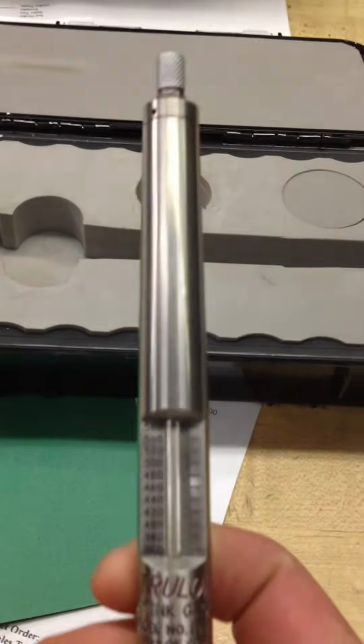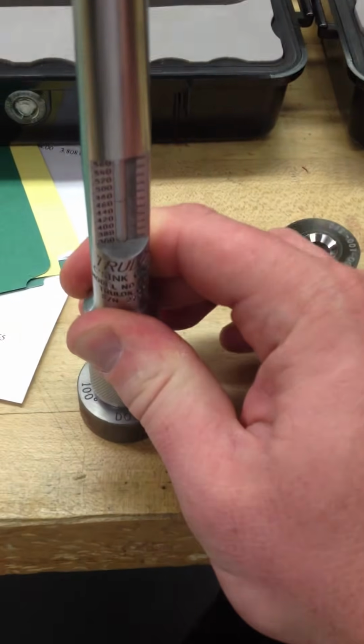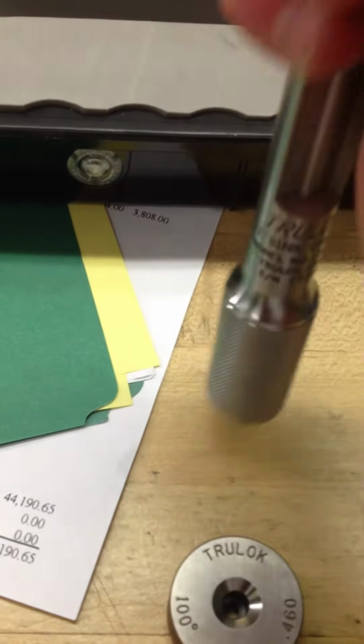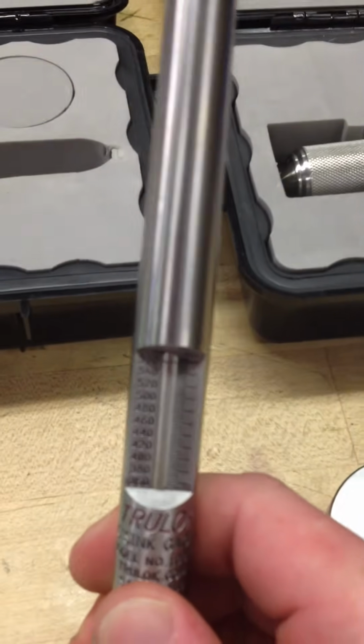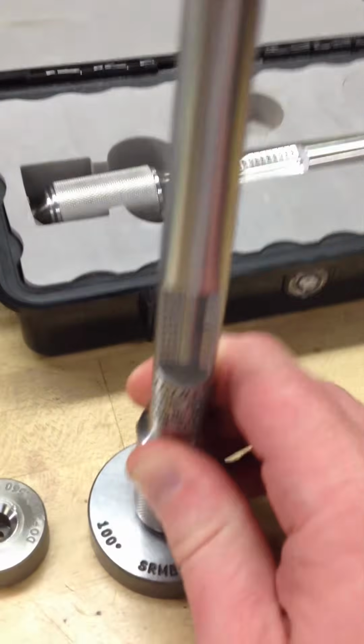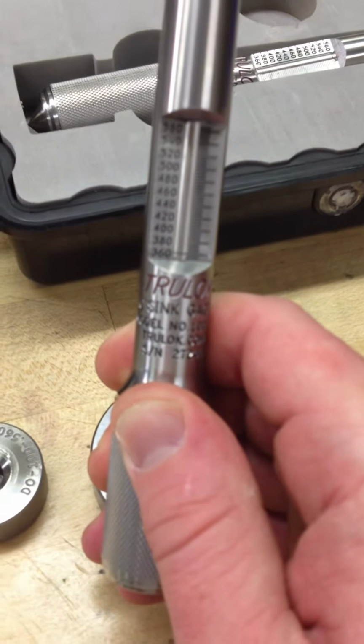So what I'll do is this. I will take this gauge, and as you can see, when you pull the pin, it clears all the way to the top, so you have full measuring range to the top. I'll calibrate it to the calibration block issued with the gauge. It reads 460. Okay, I'll pull the pin again, clear it, and now I will go to the top side, which is 560. Calibrate it to the 560. It's right at 560. Okay, now what I'll do again is I'll pull the pin and I'll calibrate it to the 360, which is the bottom side of the range, and it is measuring right at 360.